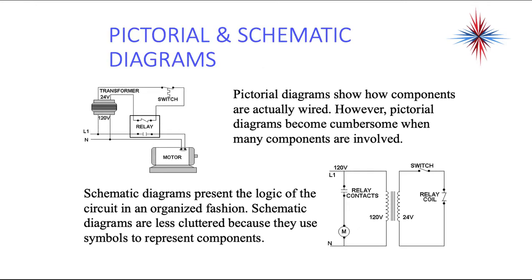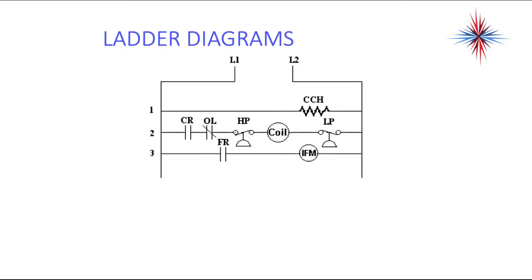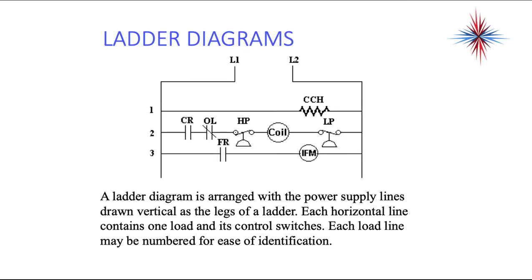Ladder diagrams have a tendency to look like a ladder. A ladder diagram is arranged with power supply lines drawn vertically as the legs of a ladder. Each horizontal line contains one load and its control switches. Each load line may be numbered for ease of identification, but is not always numbered. A lot of manufacturers do not put numbers on the side here.